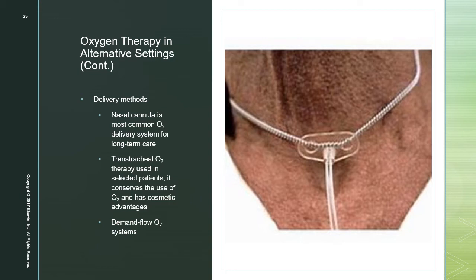Another type of common oxygen system used is a demand flow oxygen system. A demand flow oxygen delivery device, also known as an O2 conserving device, uses a flow sensor and a valve to synchronize gas delivery with the beginning of an inspiration. All the oxygen delivered during the latter half of inspiration and throughout most of expiration is wasted.